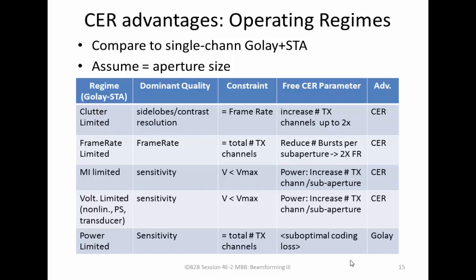By transmitting on multiple codes at different channels and amortizing the extra transmissions required by Golay over all channels, we can get: increased transmit channels in the clutter-limited case, twice the frame rate in the frame-rate-limited case, or more power in the mechanical index limited case. Golay remains better in the power-limited case, though it's unclear how you'd be power-limited with a single transmit aperture without having already hit a voltage limit, which would suggest you'd want twice the frame rate instead.